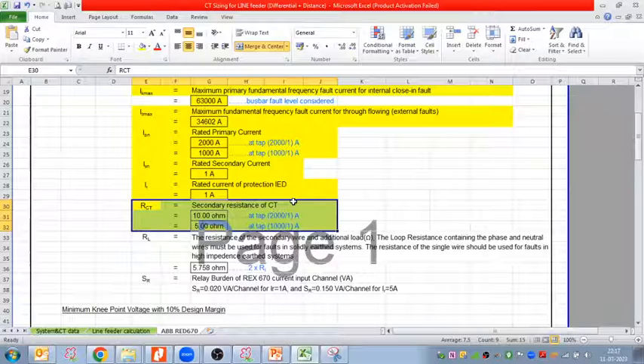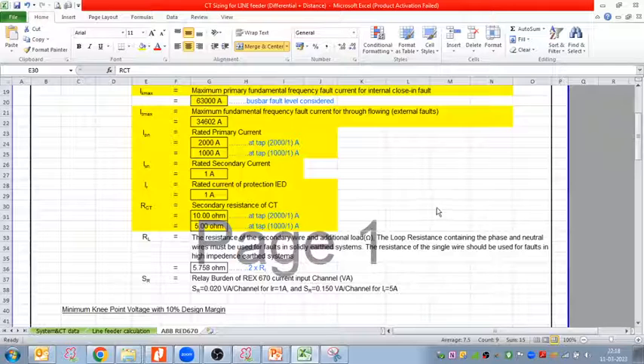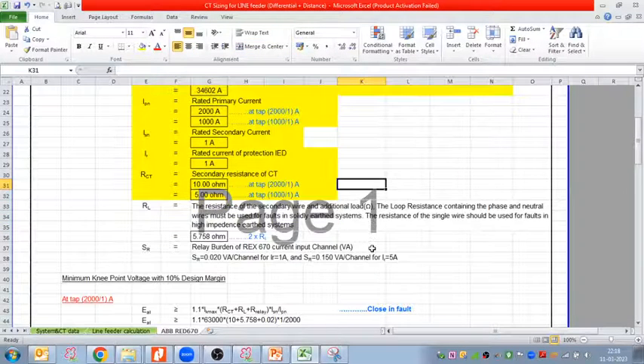Or in another case, we can take this RCT from the CT manufacturer, whichever CT we are going to use, so that RCT value we can also take as reference. And again, we have discussed that if we have executed any previous project, we can also take the RCT value from that project. Yes, the RCT value we will get from the CT manufacturers also. Yeah, Richa. Okay. So this RCT is the same as we discussed for the metering core.